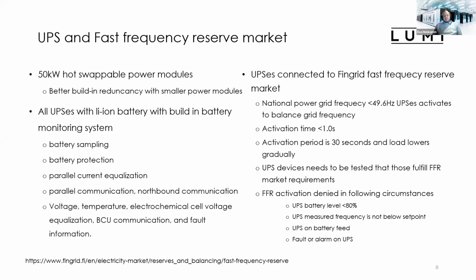There are 2 different meters that are checking the national grid frequency. The UPS has its own internal meter, and then we have an external meter, which sends the UPS a request to activate the market if this threshold is met. But if the UPS internal meter isn't showing that we are below this threshold, activation doesn't happen. And of course, if the UPS is on battery feed, activation doesn't happen, even though the national grid measurement shows that we are below the activation threshold. And if there is any kind of fault or alarm activated on the UPS device, activation doesn't happen.